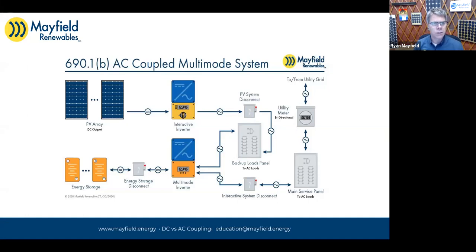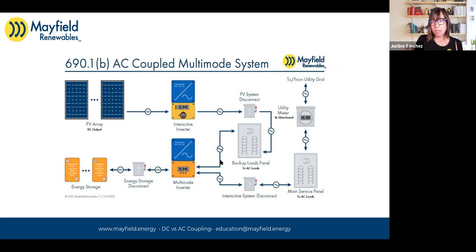It's a really good point, because what you're limited to is the capacity of your inverters. A lot of homes are used to having unlimited power, like 200 amps available at any time. But when you go into that backup mode, the off-grid mode - islanding mode, as it's called in the code - you're limited to what your inverters can pass.